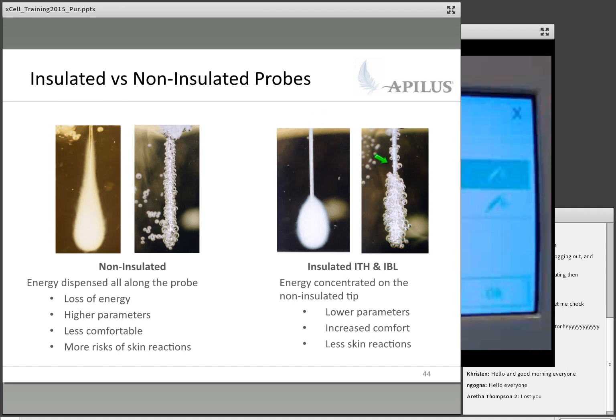You can use an insulated probe with blend, but you have to be careful into what degree the insulation covers the probe. Remember that the lye is produced evenly along the walls of the probe. It doesn't go to the tip and do a point effect like thermolysis. So you need surface area. When you're doing blend, don't pick a probe that is too insulated, where you're essentially reducing the surface area so much that the lye takes forever to produce because it just doesn't have the space to do so. So the ISO blends were created for that reason. At least it protects the top of the skin, but you've got enough surface area to produce lye.